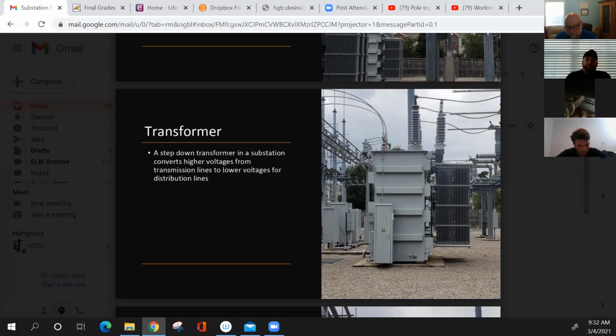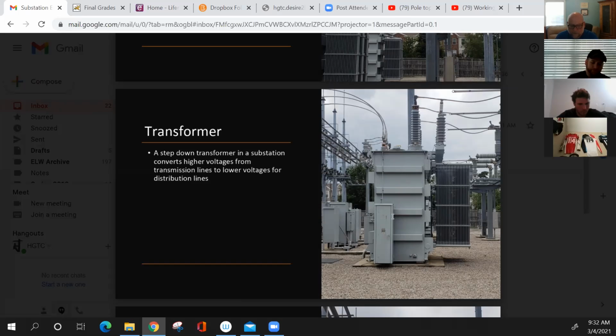It would normally take the guys from substation 2 or 3 hours to get to my substation, so I'd go check it out first whenever there was an alarm. I'd have to go check the temperature control, make sure the fans were working on the transformer itself, and make sure the transformer wasn't about to explode or pop a valve and shoot oil everywhere. So a very important part of that transformer is the cooling fins on it, and those plates and the fans itself.